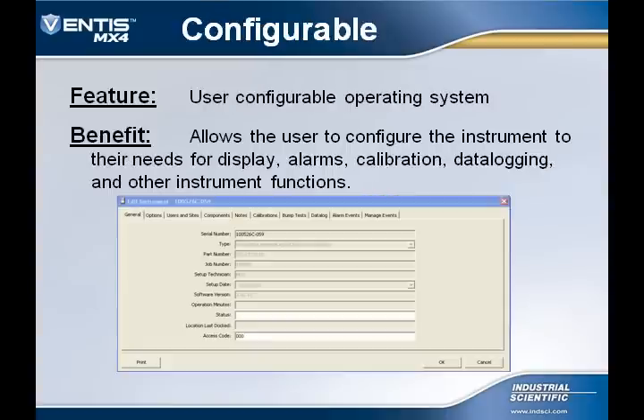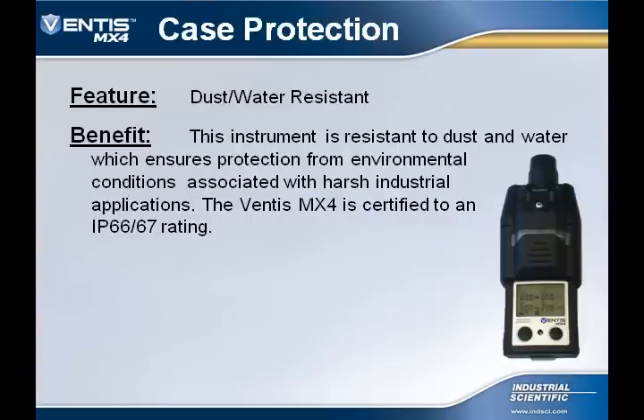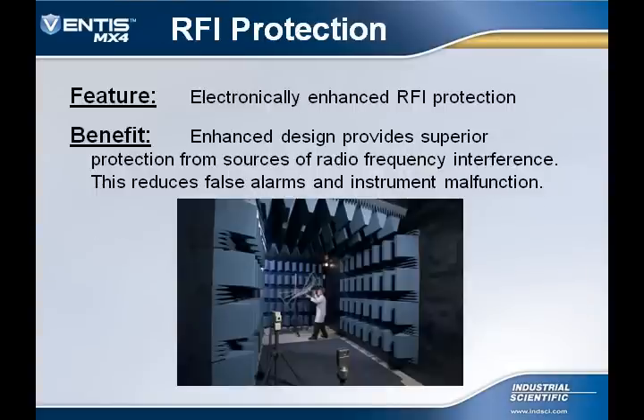The Ventis MX4 has a user-configurable operating system. This can be accessed either through the instrument's keypad, VCAL, or through the data link accessory. The Ventis MX4 is water and dust resistant, giving the MX4 superior performance in varying weather conditions. This instrument is also certified for meeting an IP67 rating. The Ventis is radio frequency interference protected, providing superior resistance to sources of radio frequency, thus reducing false alarms and instrument malfunctions.